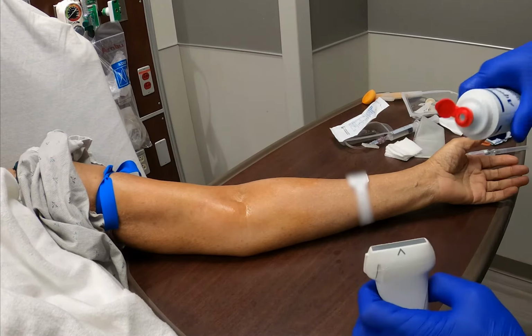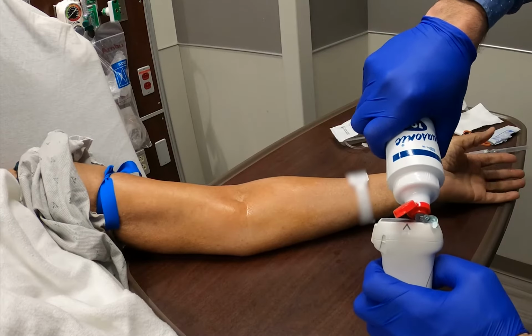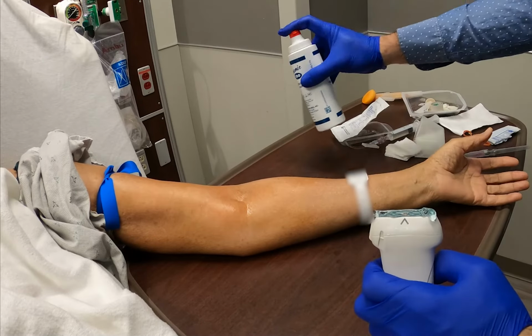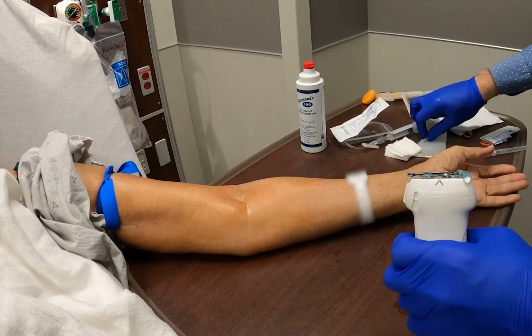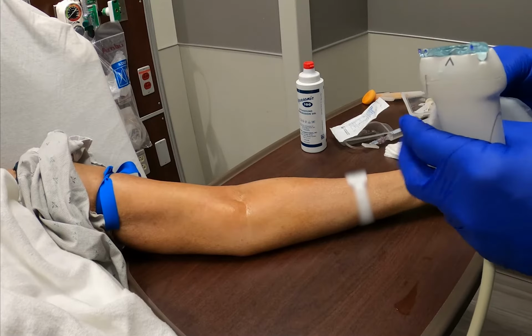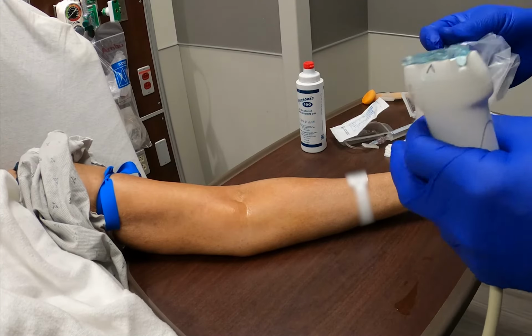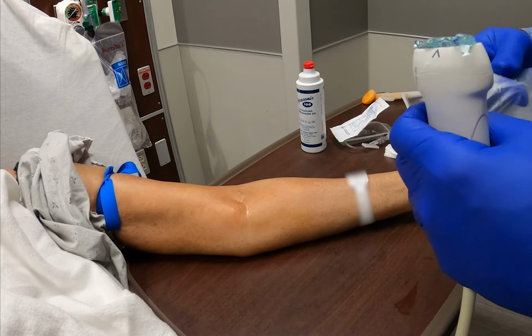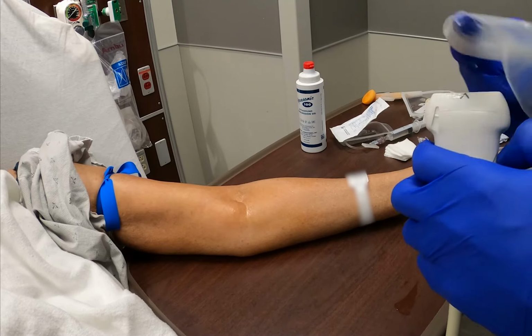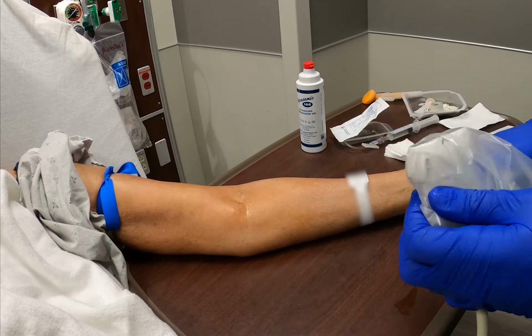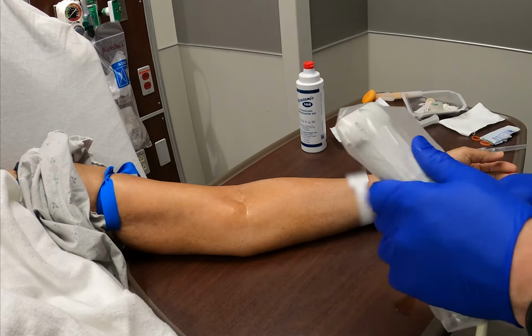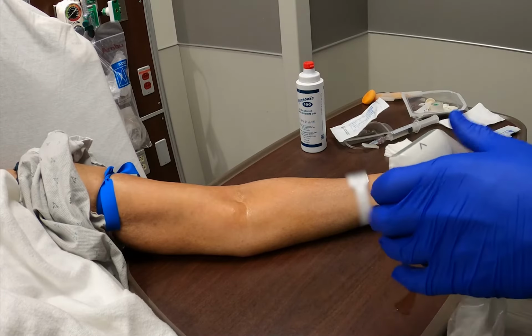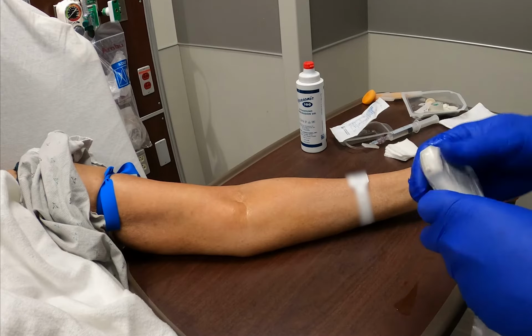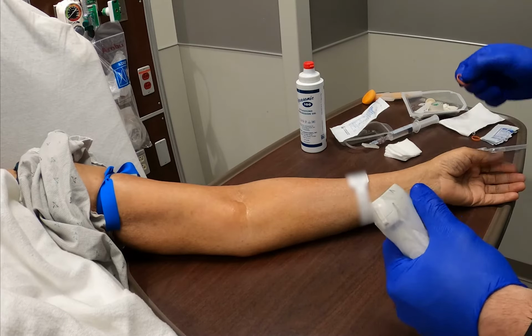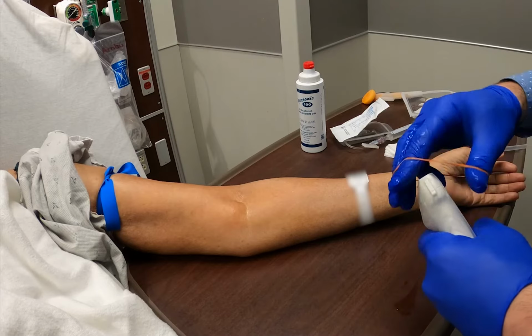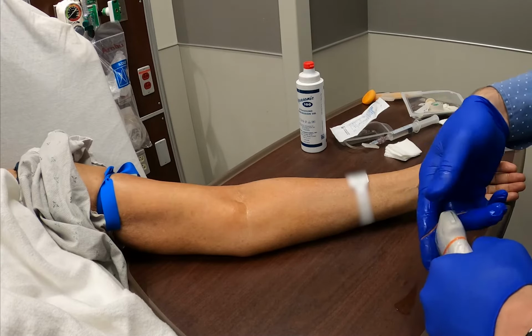Now I'm going to put a little bit of gel on the probe before I put the probe cover on, and that just helps with image quality by getting rid of any potential pockets of air that could be between the probe cover and the probe itself. Another good way to minimize the amount of interference you have from any trapped air is to wipe it off like I just did, and then use a rubber band to keep the plastic nice and tight to where you've secured it.